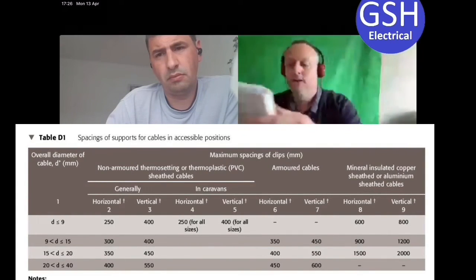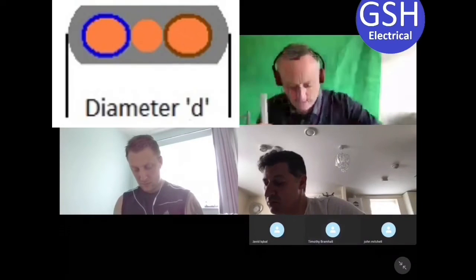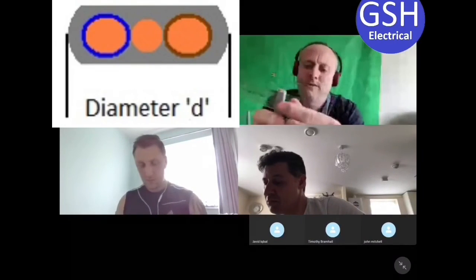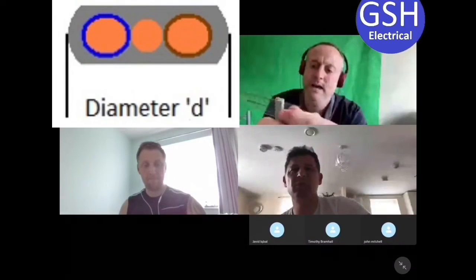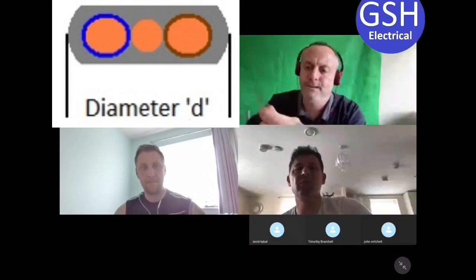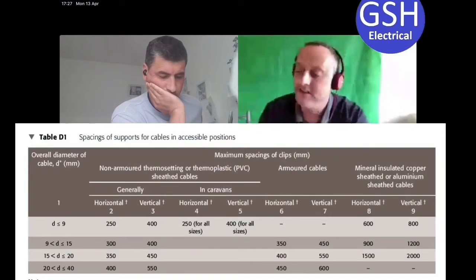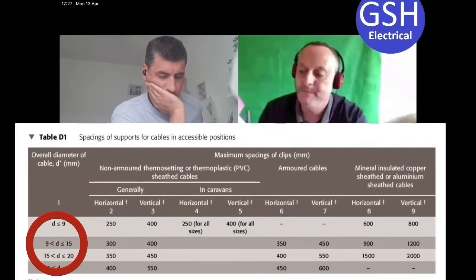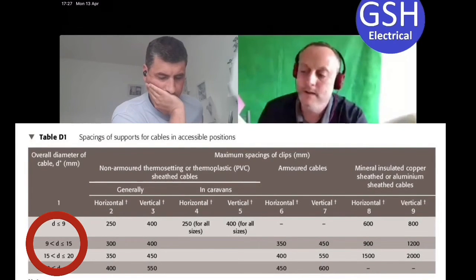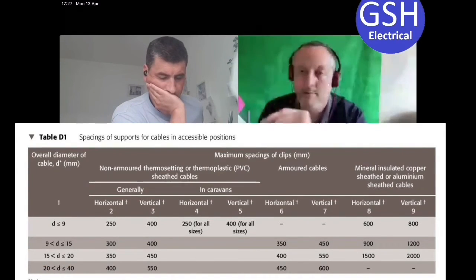Now the six mil cable - measuring it, I'm going with 13mm diameter. Back to column one, we're still on row two because we're not exceeding 15mm. So the clipping distance remains the same as the two point five - 300mm horizontal and 400mm vertical. That makes logical sense.